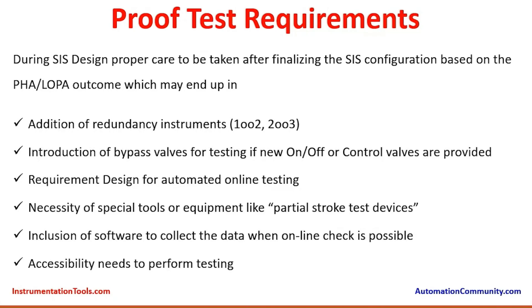During system design, proper care is to be taken after finalizing the Safety Instrumented System configuration based on the PHA (Process Hazard Analysis) and LOPA (Layer of Protection Analysis) outcome. Based on these studies there could be some additional requirements on the SIS, such as: addition of redundancy instruments like 1oo2 or 2oo3 voting; introduction of bypass valves for testing if new on/off or control valves are provided; and a requirement to design for automated online testing, where isolation valves are closed provided there is enough bypass arrangement for the process to continue operations.